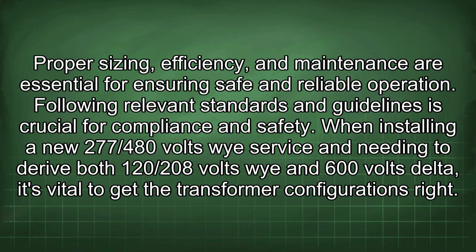When installing a new 277/480 volts Y service and needing to derive both 120/208 volts Y and 600 volts delta, it's vital to get the transformer configurations right.